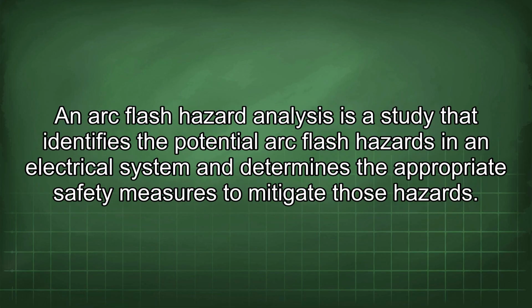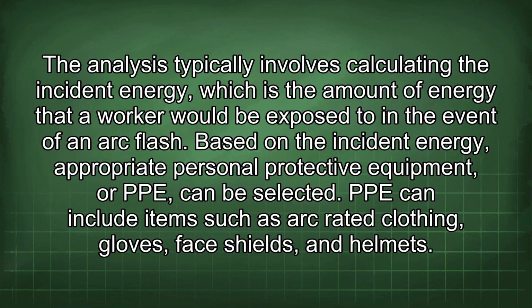An arc flash hazard analysis is a study that identifies the potential arc flash hazards in an electrical system and determines the appropriate safety measures to mitigate those hazards. The analysis typically involves calculating the incident energy, which is the amount of energy that a worker would be exposed to in the event of an arc flash. Based on the incident energy, appropriate personal protective equipment, or PPE, can be selected. PPE can include items such as arc-rated clothing, gloves, face shields, and helmets.